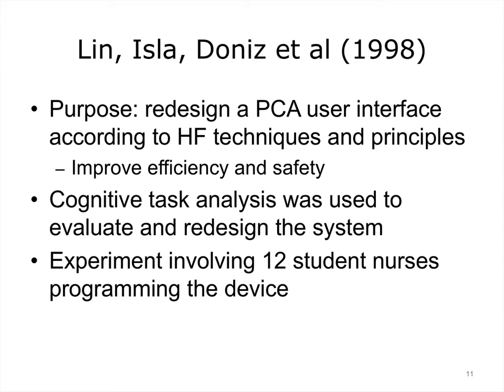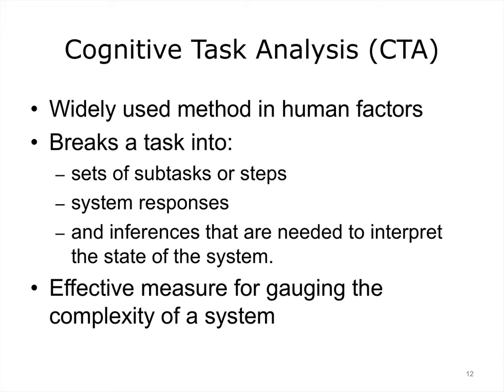Lin and colleagues investigated the effects of two interfaces to a commonly used PCA device, including the original interface. Based on a cognitive task analysis, they redesigned the original interface so that it was more in line with sound human factors principles. Cognitive task analysis is a widely used method in human factors. It breaks a task into sets of subtasks or steps, system responses such as changes in the display as a result of an action, and inferences needed to interpret the state of the system. It is an effective measure for gauging the complexity of a system — for example, a simple task that necessitates 25 steps or more to complete using a given system is likely to be unnecessarily complex.